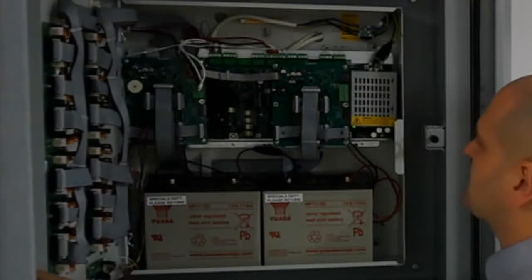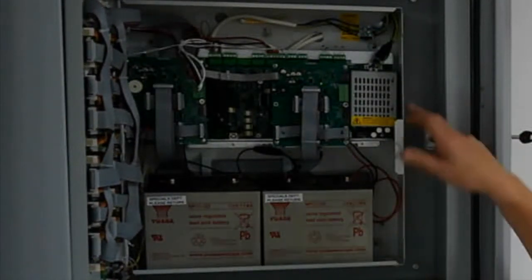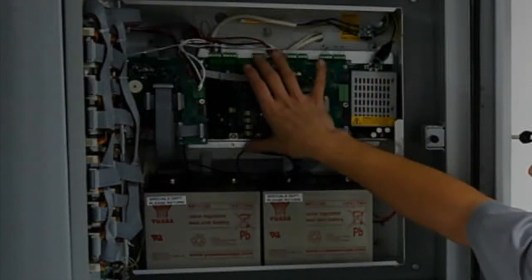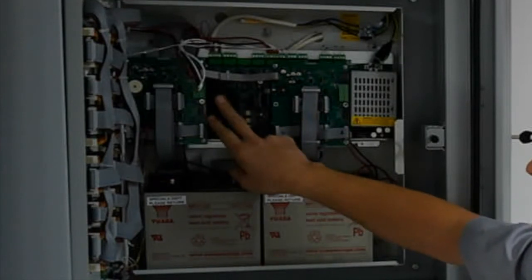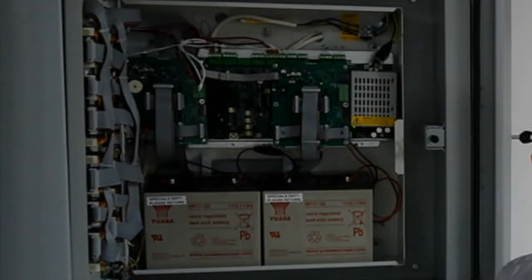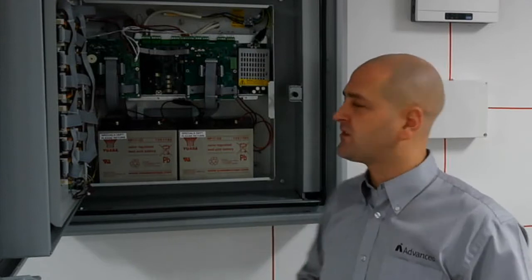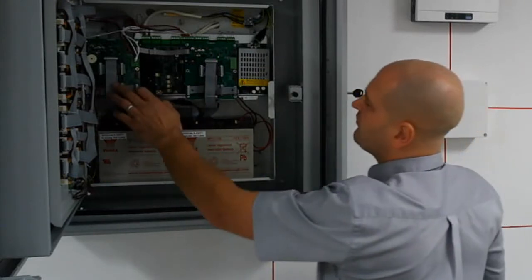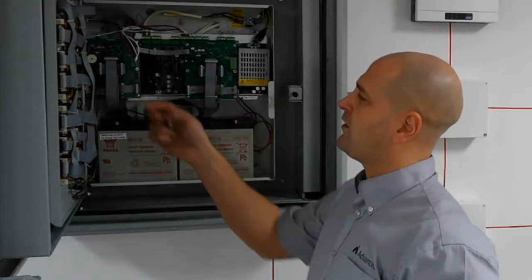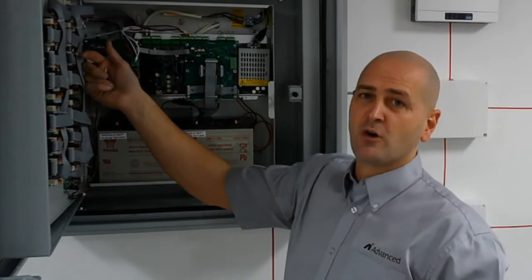But components, the infrastructure of the product, to give you an overview, you have your 4 loops. This is a 4-loop system, but it's only got 2 loop cards fitted. We can easily expand the system simply by inserting our loop card. The loop card is what's driving the sounders connected to the system. So we then have 2 48-way IOs. The 48-way IO technology is used to drive or to communicate internally with the fire and rescue service toggle switches.